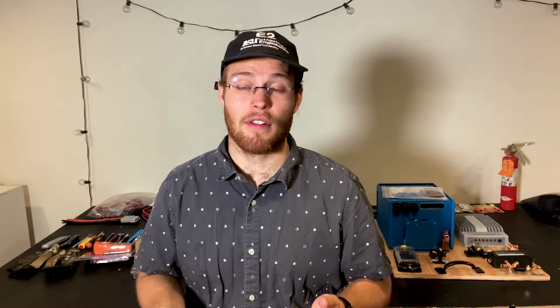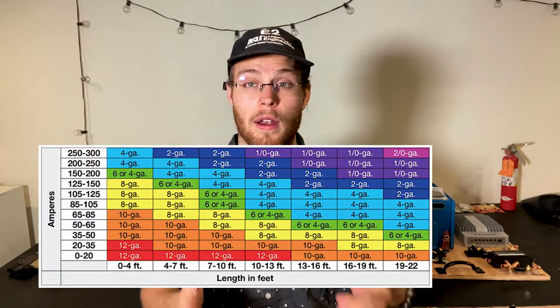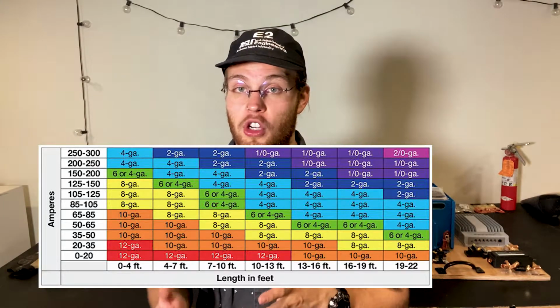First of these, you want to think about wires. Choosing the correct wiring is extremely important. If you choose the wrong wiring, you can run into problems: voltage drops from internal resistance, or worse, overheating that could start fires. You want to buy wires correctly rated for the amperage traveling across them. There's an awesome chart you can see here showing what wires you need for what amperages at what distance.